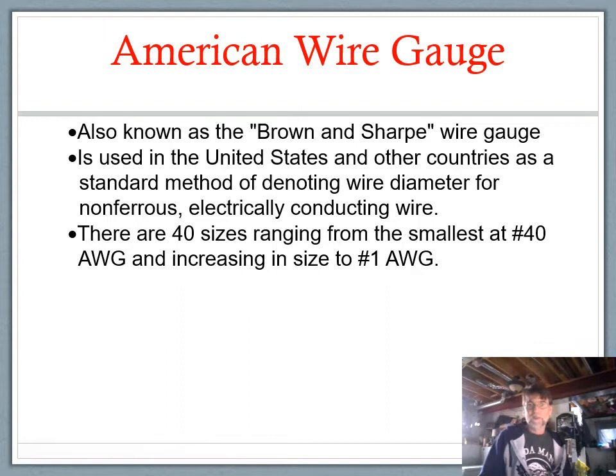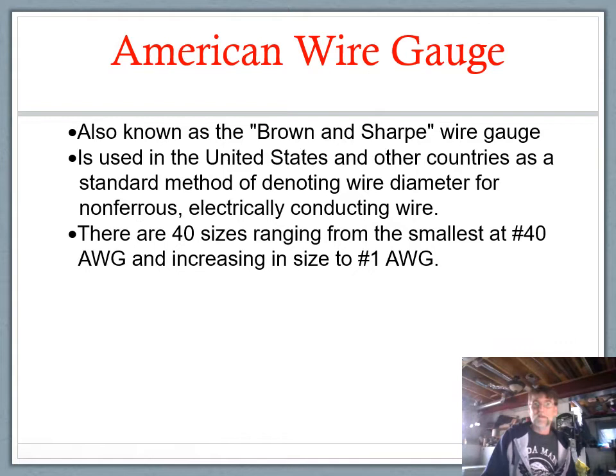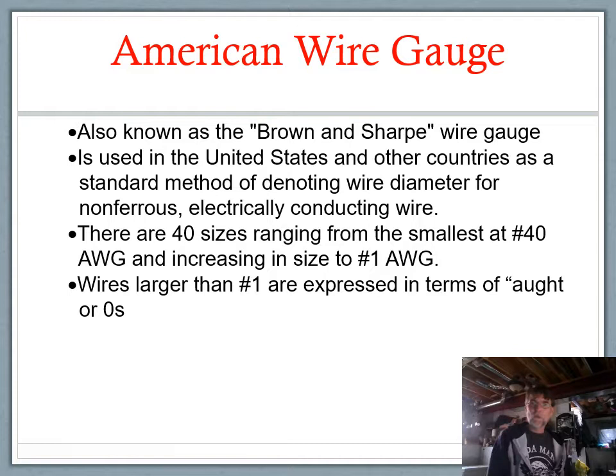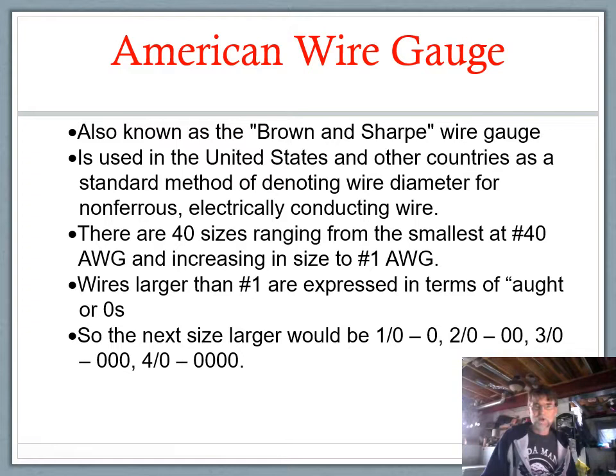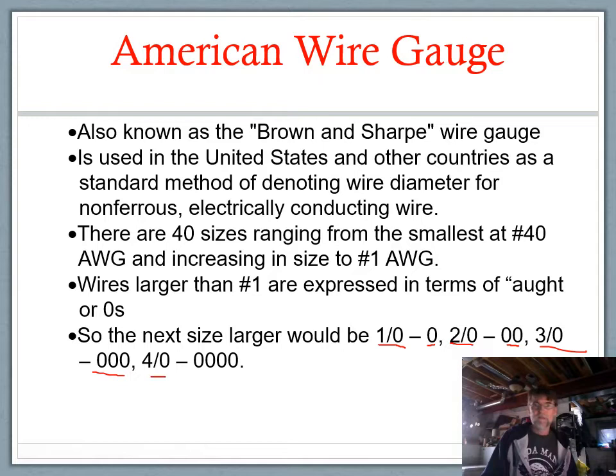Typical wire in your house is 14 gauge or possibly 12 gauge. When you get up to number one, you're almost at the size of service conductors. Once you get bigger than number one AWG, we have four sizes referred to as 'oughts.' You might write one ought as '1/0' or with a single zero. Then two ought is two zeros, three ought is three zeros, and four ought is four zeros. These are typical sizes for standard residential service.